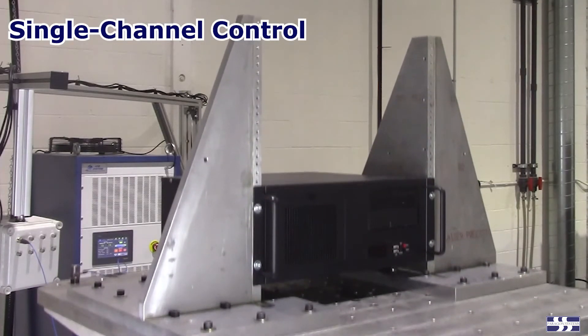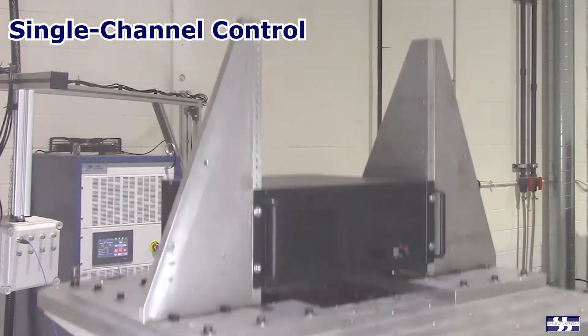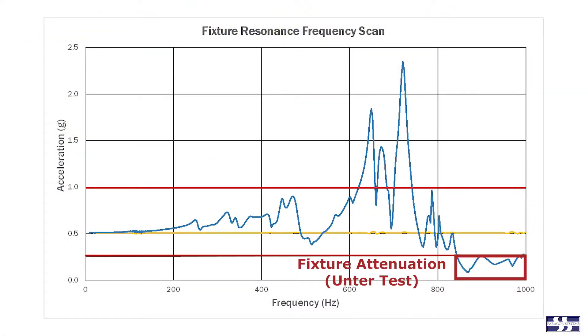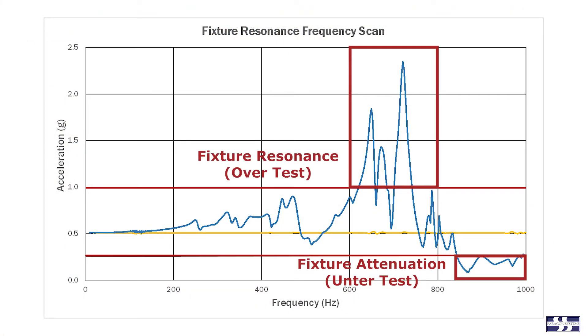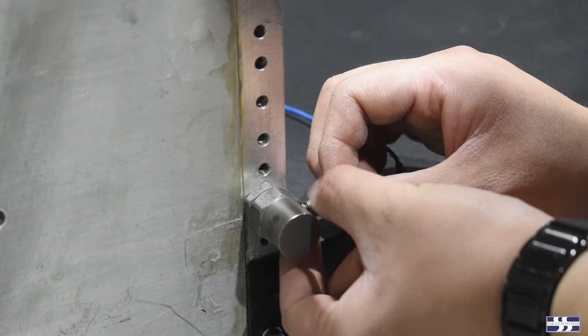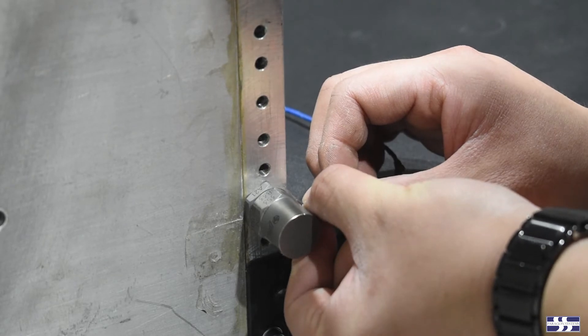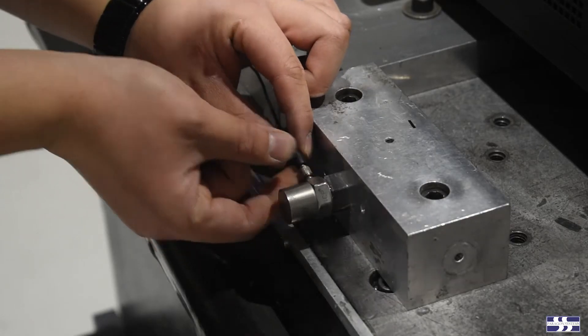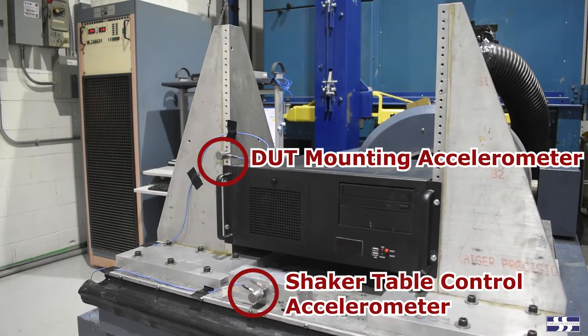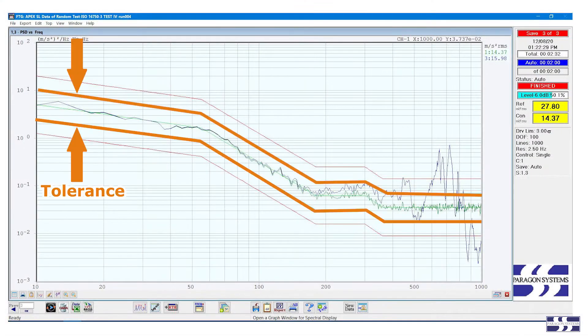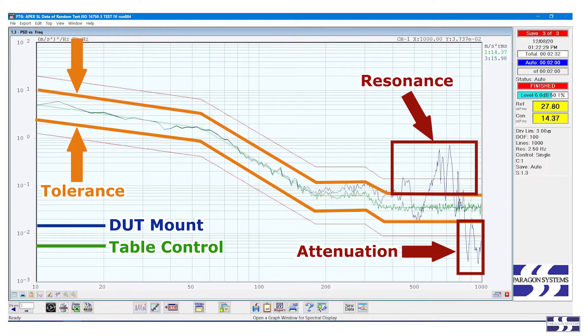If the fixture does exhibit resonances or attenuation regions within the frequency range of the test profile, these characteristics may be concealed with single-channel control. Attaching additional accelerometers to the DUT mounting points can reveal if the fixture resonances or attenuation are shifting the test profile out of tolerance at the DUT mounting points.